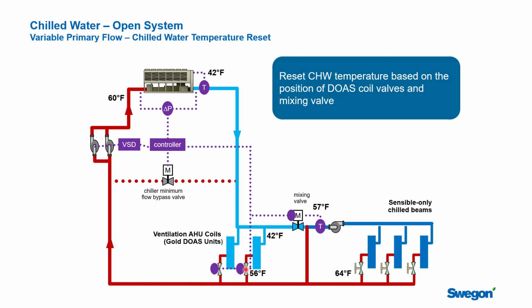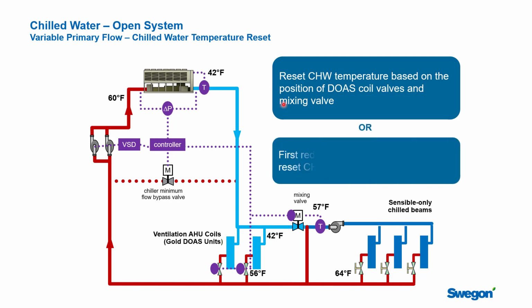And if you find that this valve starts to go wide open, because it's trying desperately to cool the air down enough to dehumidify it, that will give you the information you need about how much reset you can get. Another way to consider doing this would be, first you slow down the pumps with an algorithm, and then you would start to do the chilled water. So let me show you what that might look like.